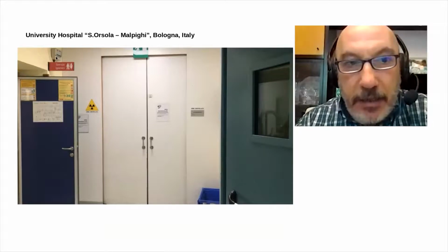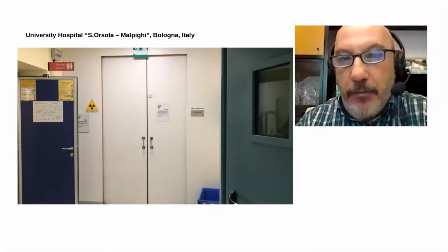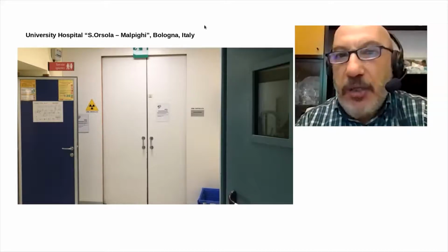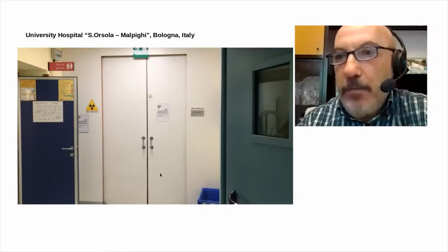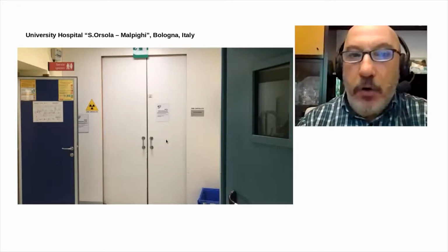You can see here in this corner, there is a radiation monitor checking the door. It is calibrated with a properly set threshold so that if a patient inadvertently exits from the department, an alarm is produced and the nurses can check what is going on.